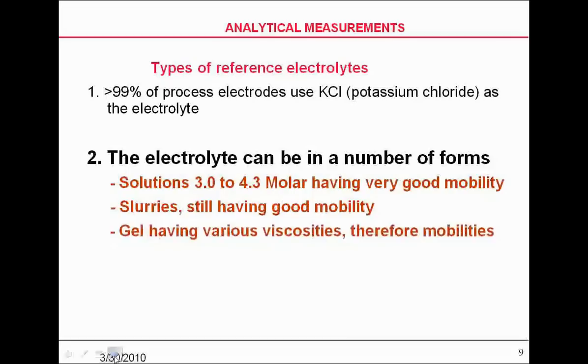In our industrial probes, we use a gel of potassium chloride because it has good viscosities, and its mobility, while good enough to make the measurement, is in a gel form so that it's slow to migrate into the system.